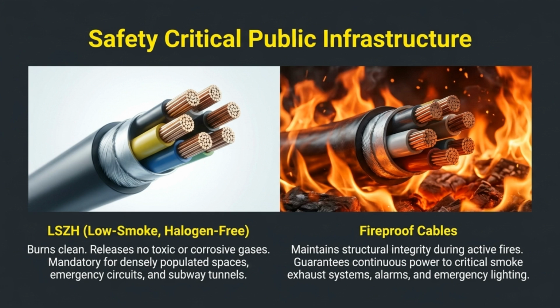Safety is critical in public infrastructure. LSZH cables are mandatory for crowded spaces, releasing no toxic or corrosive gases when burning. Fireproof cables maintain integrity during active fires, ensuring continuous power to critical emergency systems.